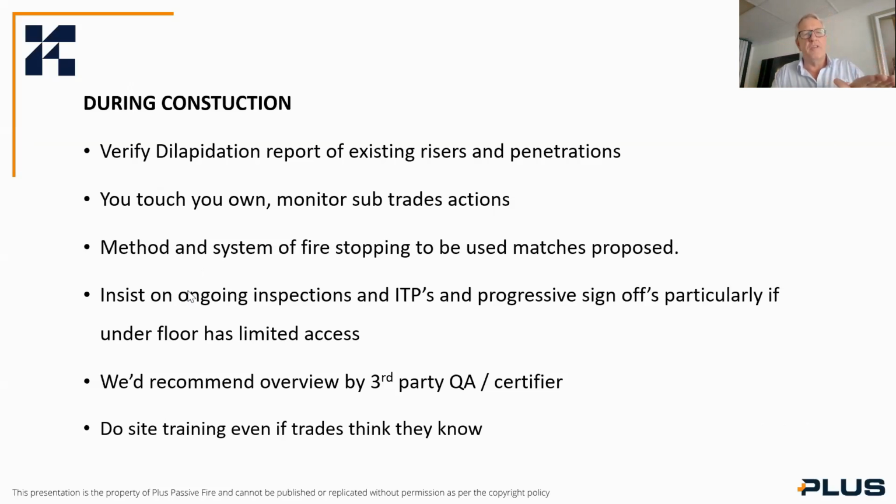I would insist on an ITP, inspection test plan, and progressive sign-off, particularly if you're doing works through the floor into the tenancy underneath. There's a lot of that goes on. You want to make sure that everyone's doing that at the same time. You would generally do that as part of your programming, because depending who's down there, you might have to get security and whatnot. But if you're going down there to do the work, do the fire stopping, do the labelling, create the evidence, close the ceiling up and get out of there and don't go back.